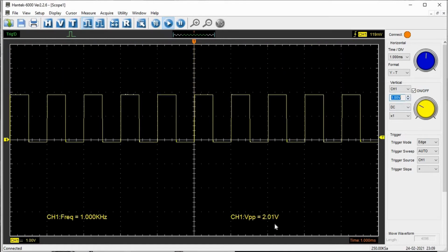So you have to make sure that the test signal, that is 1 kilohertz and 2 volts, is coming correctly here. If it is an older type probe, then it will not show it on the display here, so you have to make sure that the frequency and amplitude are correct by using the scale or the graph they have given here.